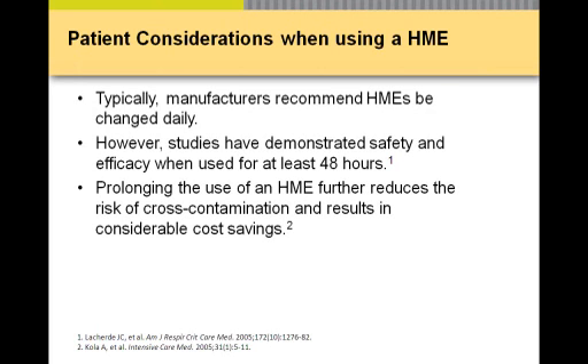Most manufacturers recommend changing HMEs daily. There are, though, HMEs out there that will run for 72 hours without having to be changed. So again, the less you have to break the circuit and can use an HME for a longer period of time without having to change them in and out, perhaps there is a benefit there, not only in cost but also in reduction of risk of ventilator-associated pneumonia.